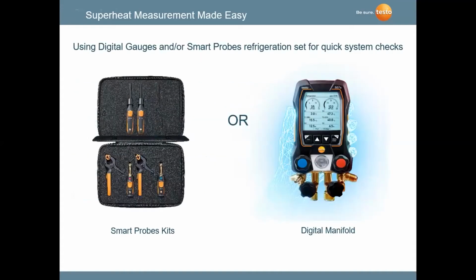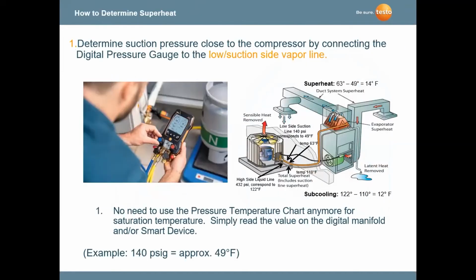Today, we're transitioning very quickly to ways of getting away from the analog gauges. There's a whole variety of digital instruments that you can get into, using digital gauges, from what we call smart probes, independent probes with no hoses that go directly on the service ports, or we can use hoses with the digital gauges and also get the superheat and subcooling.